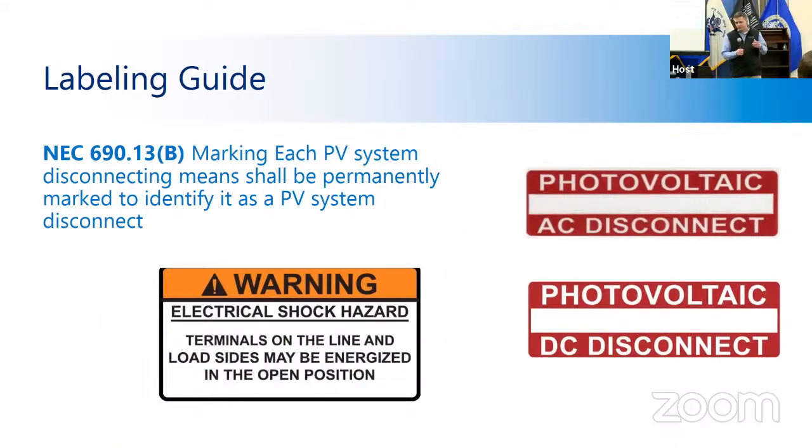All right, so the NEC, the National Electrical Code, also requires these markings on PV systems. Like I said earlier, electrical shock hazard, and also the disconnect labeling, whether it's AC disconnect or DC disconnect. Again, in a normal situation with no solar, if you shut the disconnect off, you have no power, right? If the sun's out and you do have a solar system, you shut off the service disconnect, you still have power, right? And if you're not expecting that, that's potentially fatal. So it's very important to label those, like I said, and the labels should last the life of the system.